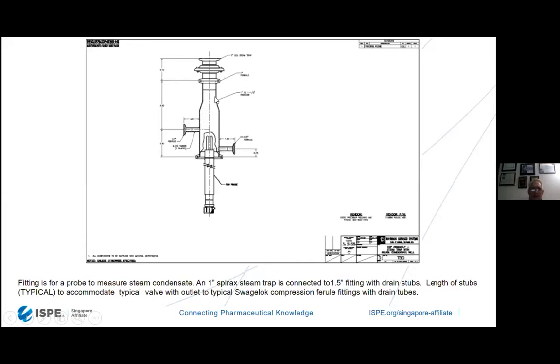configuration of a device. It's a vessel, actually, just a spool piece. That particular spool piece will have inserted into it the Rouge monitor with its probes, and then allowed to have the information from the water go over to the SCADA system. This has a valve at the top, which is the upper limit of the water entrapment. Bottom valve is usually closed. So the idea here is we entrap the water. Even though it's not a one-to-one function of what's going on with the steam system, it's indicative of how the rouge is developing inside the steam system and can be used to show the frequency for derouging passivation.